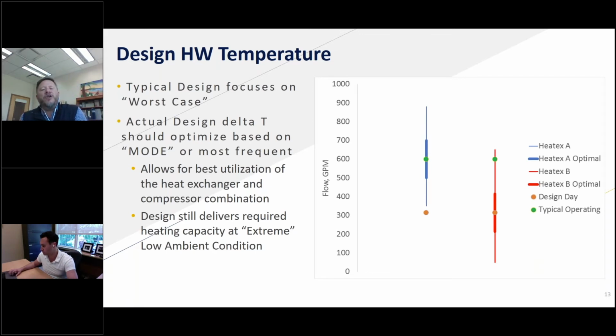Essentially that means, where is the largest occurrence? Where's the largest number of hours that we're actually running our system? From that standpoint, we should be looking at our capacity requirement there, as well as the flow required for the delta T that we would desire. When we do that, the line on the left, the blue line, shows our typical operating point, or that mode point, being in the very middle of that heat exchanger design. That is where we really want to reside as much as we can. The orange dot is what would be considered the design day. If you look at that, we're slightly outside of the operating envelope of that heat exchanger that we're using.